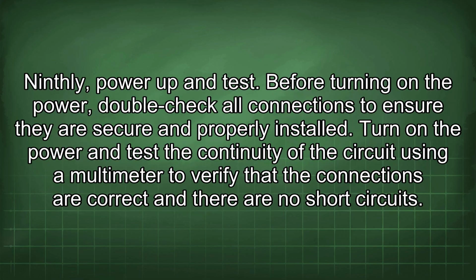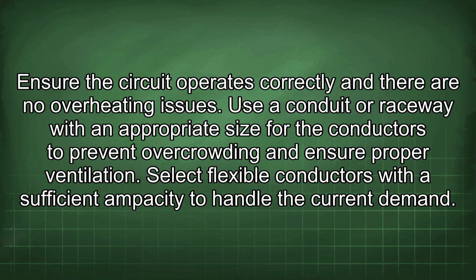Ninthly, power up and test. Before turning on the power, double-check all connections to ensure they are secure and properly installed. Turn on the power and test the continuity of the circuit using a multimeter to verify that the connections are correct and there are no short circuits. Ensure the circuit operates correctly and there are no overheating issues.